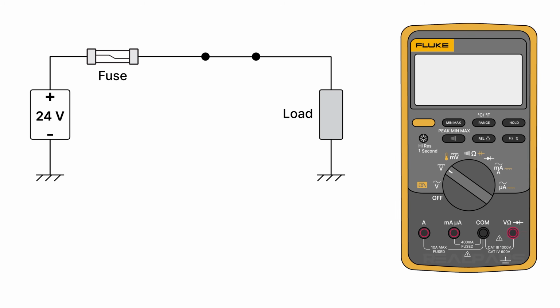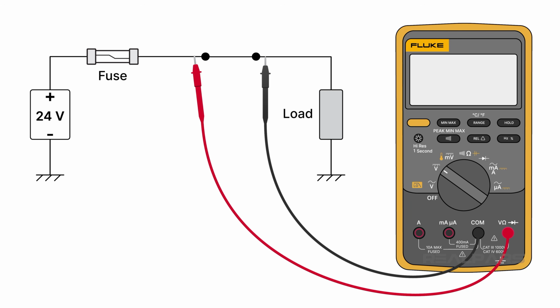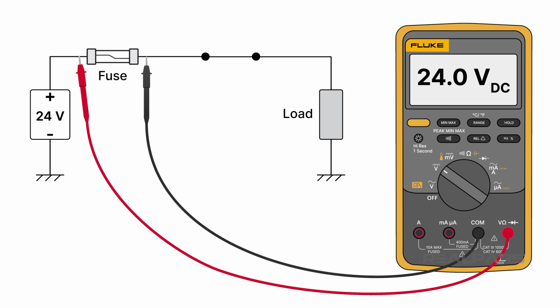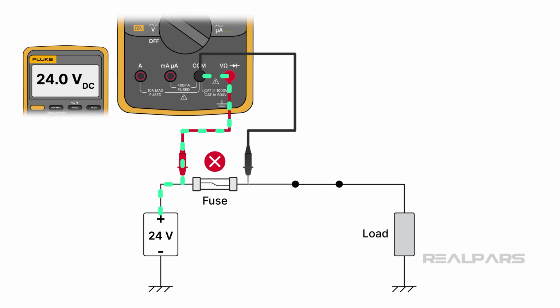If you place your meter leads across a good closed switch in a 24 volts DC circuit, you will read 0 volts DC. If you read 24 volts DC, the switch is open. If it's supposed to be closed, you've got a bad switch. Similarly, if you measure 24 volts across a fuse, it goes into the garbage. Why is there a 24-volt drop across an open circuit? This can be explained using Kirchhoff's voltage law, which states that the sum of the voltages around a closed loop is 0. As soon as you connect your multimeter to the circuit, you've closed the loop.